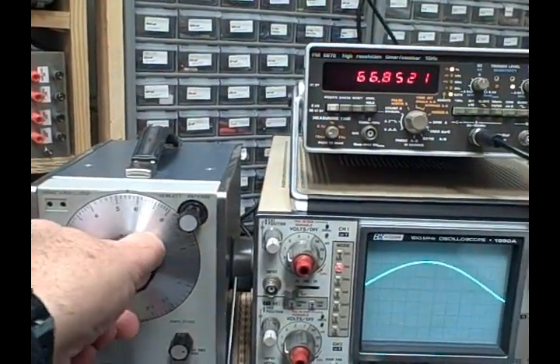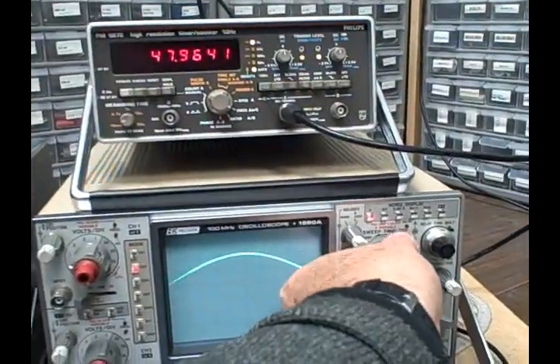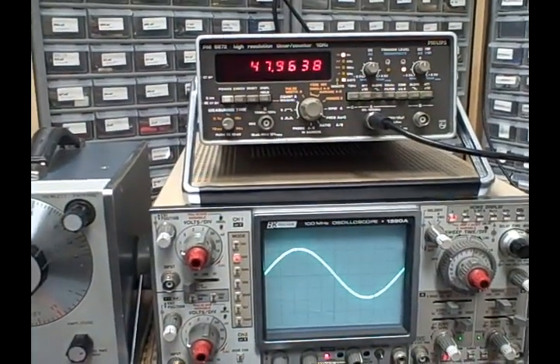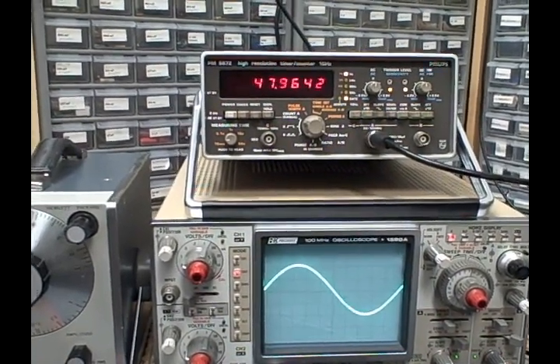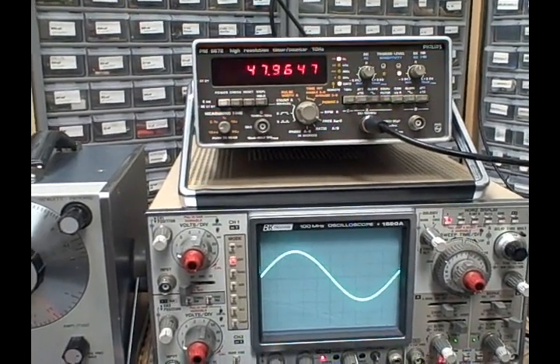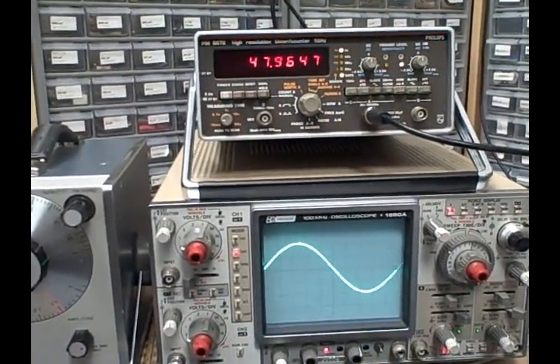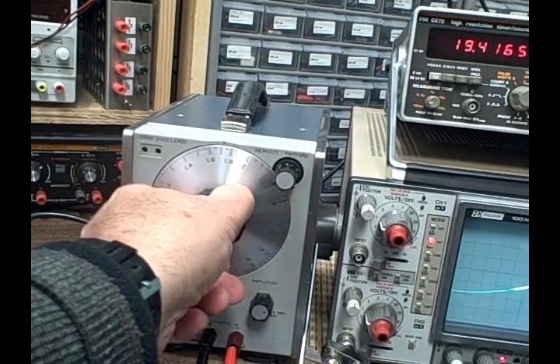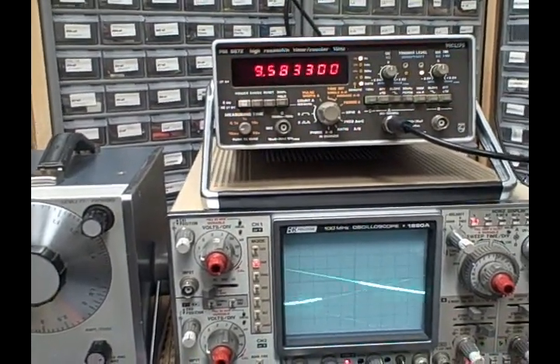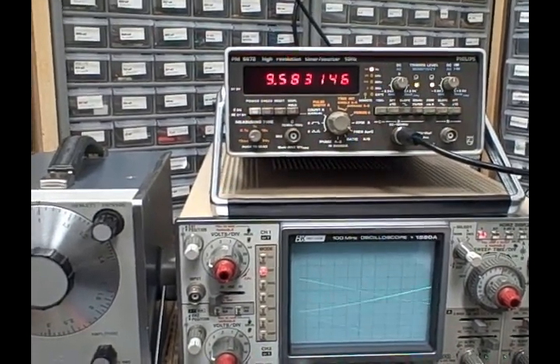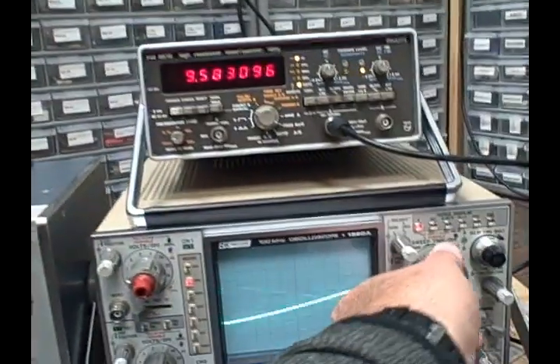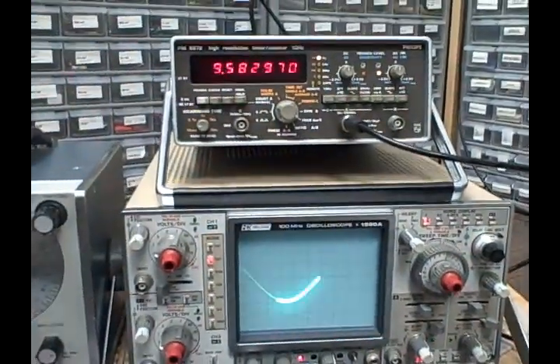Let's take her down to 5. And we're getting 1 trace in 10 divisions at 2 milliseconds per division which would put us at about 50 hertz. And we're reading 47.96 or 48, so we're within 2 hertz of 50. Take her down to 1, and we would want to read 10 hertz because it's times 10. We're reading 9.58, so we're within 0.42 hertz of 10 hertz. And we can certainly display a trace there.